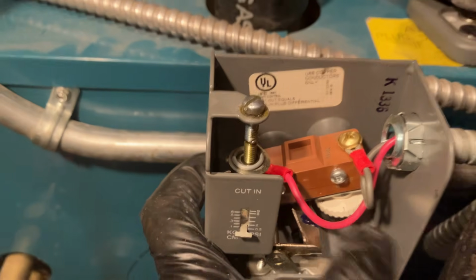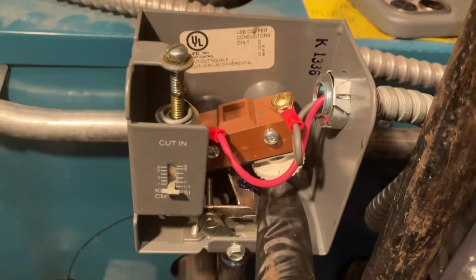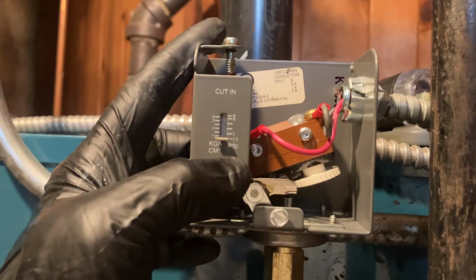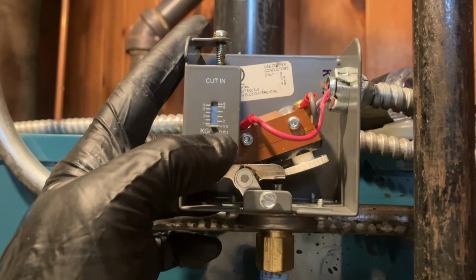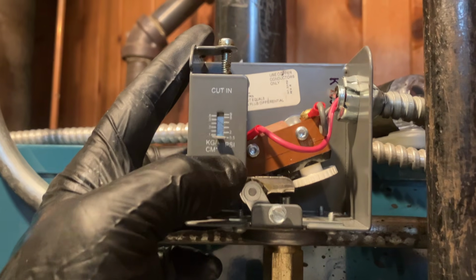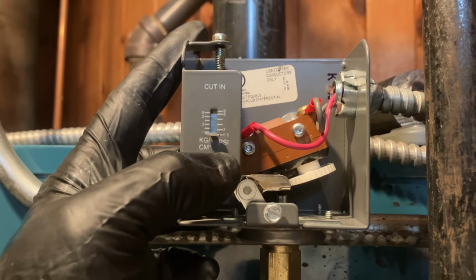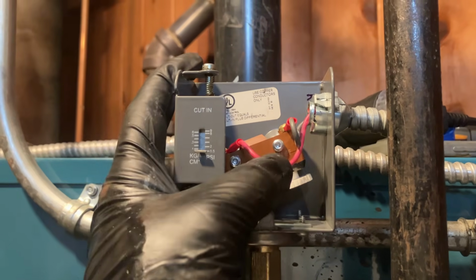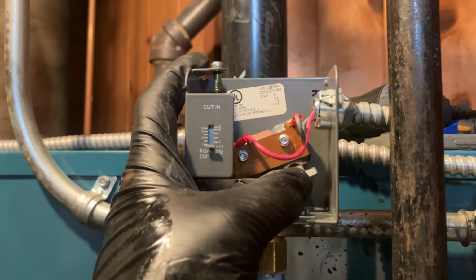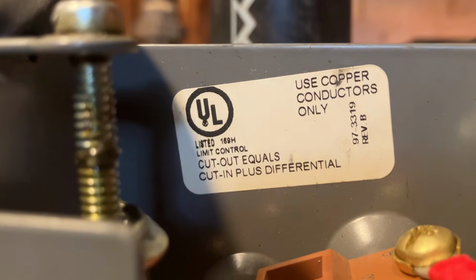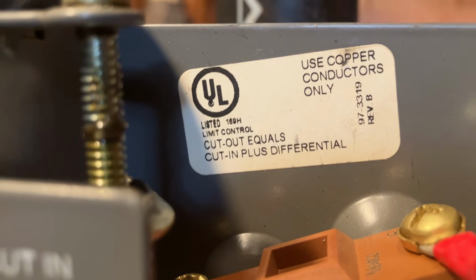All right, pressure control's reinstalled. Our differential set to 1 and our pressure is set to 0.5. Wow, you never see that. Cut in plus differential equals cut out. It says it right there, actually. Cut out equals cut in plus differential.